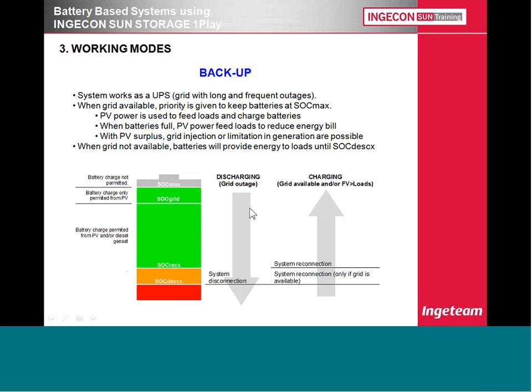A second difference is this other line that I have drawn here. This is also optional. This is from non-critical loads. In systems like this, sometimes people want to connect things in a way such that if there's a blackout, some specific loads stop working. For example, the aircon. Imagine that you have aircon in your office, and when there's a blackout in the grid, you don't mind the aircon stopping as long as the rest of the things keep working, right? Imagine that you have a fridge, whatever element. Those critical things will be connected here. The non-critical things, those that you don't mind getting disconnected, will be connected here. So when the grid disappears, this will stop working, and the rest will be fed from batteries, or the optional PV power.